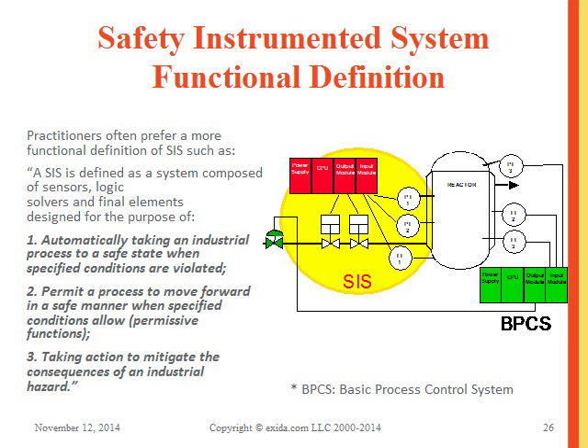A more functional definition: a SIS is a system composed of sensors, logic solvers, and final elements designed to automatically take an industrial process to a safe state when specific conditions are violated, permit a process to move forward safely when conditions allow, or take action to mitigate the consequences of an industrial hazard. A SIS is similar to a basic process control system in that both have sensors, logic solvers, and final elements — however, a SIS operates in a completely different mode with unique design, maintenance, and mechanical integrity requirements.